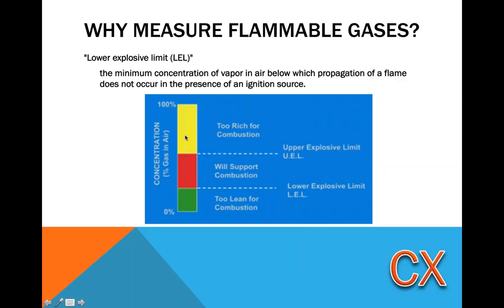Now you notice this is green, red, and yellow. Yellow does not mean safe like green does, because in an area where it's too rich for combustion, you're above the upper explosive limit. The dissipation of the gas, or the introduction of fresh air, can cause it very quickly to drop into a range where it will support combustion, and then it becomes a flammable atmosphere, which you don't want to enter into.